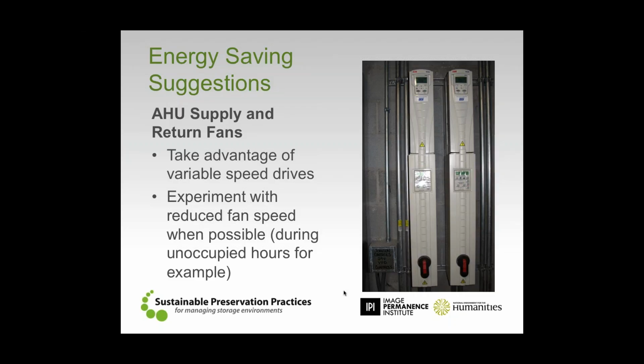And as we take this dimmer switch, if you will, or take the variable speed drive and slow the fan down, it means that we're decreasing the amount of air that goes over the coils and goes out into the space. What we found in research is that reduction of air quantity, especially when we start looking at seasonal operation, is certainly a good possibility for trying to reduce energy consumption, but still oftentimes maintain the preservation conditions that we have in spaces.